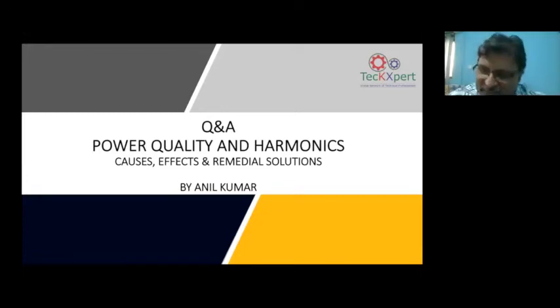In fact, that is why in the beginning slides I was telling about all the various power quality problems one can encounter in a facility. The harmonics can be many times a cause, but sometimes the cause need not be reflected as harmonics. Because if you have a little amount of harmonics in the network, let's say a 20 ampere or a 50 ampere harmonic current in a 1000 ampere network, it's very small. 50 ampere is nothing to worry about. But the problem is this 50 ampere fellow can cause a catastrophe later.